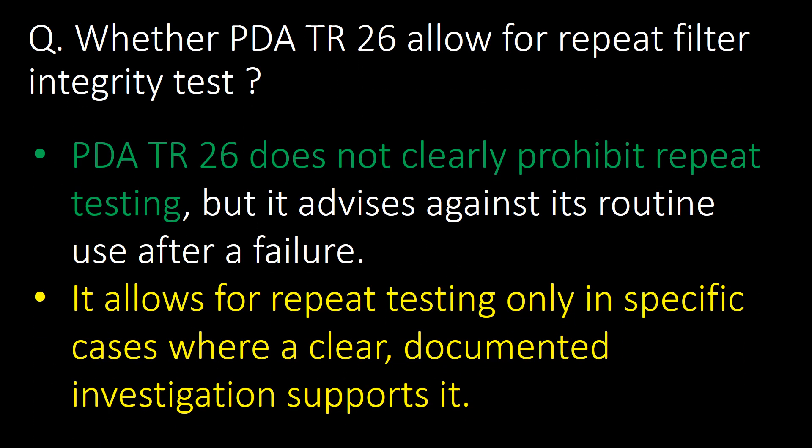Welcome. First, a very basic and direct question: whether PDA Technical Report No. 26 allows for repeat filter integrity tests. PDA's Technical Report No. 26 does not clearly prohibit repeat testing, but it advises against its routine use after a failure. It allows for repeat testing only in specific cases where a clear, documented investigation supports it.